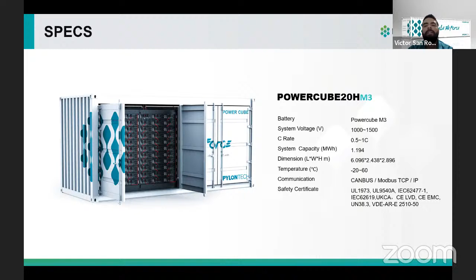This is almost the same, just the batteries are different. These are the M3; the past one was M1. This one is a little bit smaller, for 1.1 megawatt hours. The battery module is this one, the M3A, for a battery of 5.68 kilowatt hours, and the controller is different.